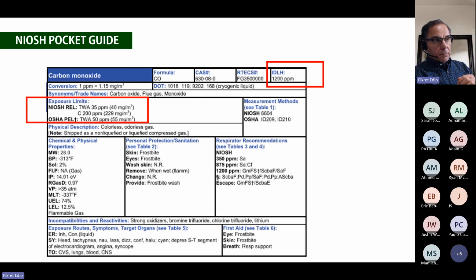Believe it or not, for the past 20 plus years that I've been working, I received mechanical drawings from engineers, and most of the time I can see this is being cut and pasted from somewhere. It says you set your alarm set points for CO at 500 ppm. Well, no, you cannot set it to 500 ppm. So I pick up the phone, I talk to the engineer, and I say I can't set it up to 500, because the contractors will follow that blindly. Now it's up to me, up to you, that we talk to the engineer and give them an educative discussion. We say, if you look at the NIOSH pocketbook, this is where we should be setting our alarm set points, and this is why.